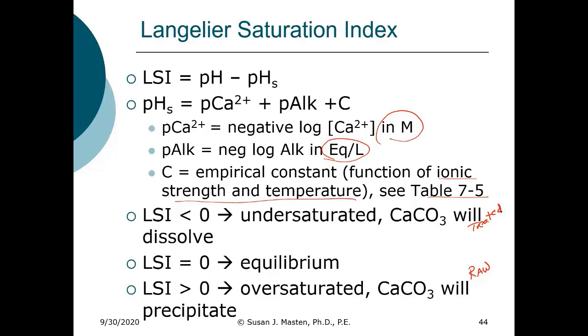So you have a water that treatment has shifted the equilibrium from oversaturation to undersaturation, and that would have potentially dissolved the calcium carbonate that would have been on the inside of pipes that provided this protective coating. That's something you almost never hear about, but it's something that actually did occur, and it really was a function of the treatment. The Flint River water itself was oversaturated.